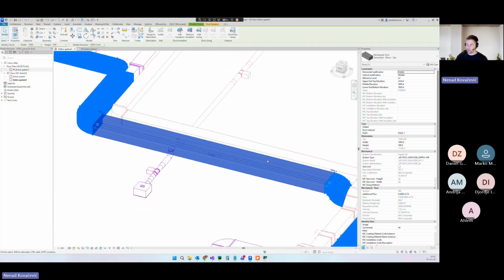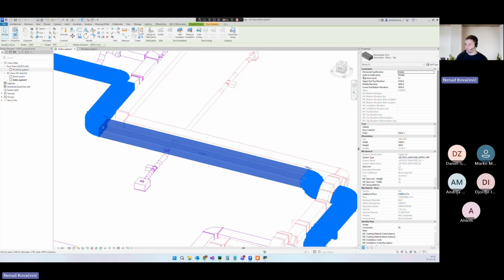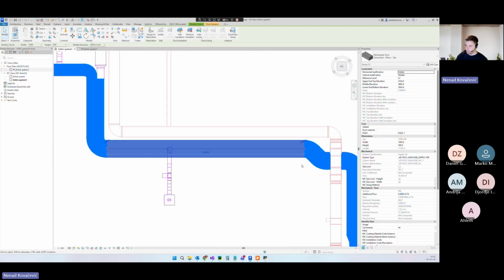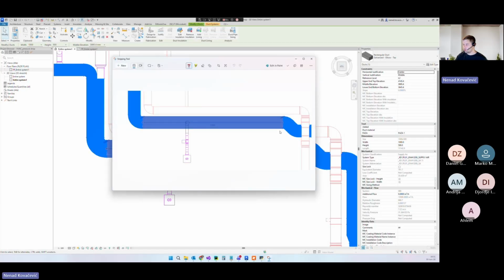It is not split in any way, and because we need to calculate to this air terminal, we need to split this element into two in the calculation, because I don't know the length. It's 11 meters, and we will say okay, because we have a tap over here that is 9 meters, and over here we will have 2 meters. Whatever its ID, for us this is a 0, and this element ID is with a 1.